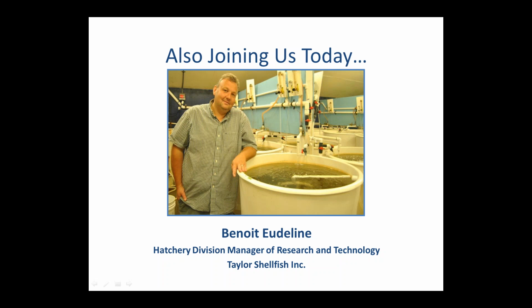I'd like to address another point that Todd mentioned about discrete sampling and co-located sensors. It was a very important point that Todd made about discrete sampling and how close can you be to your probe when you take this discrete sample. And I think that's probably one of the challenges we are having in our location, because the water quality can fluctuate quite fast at times, and again, collecting a discrete sample can be quite challenging, to make sure that you have the same water that the probe is measuring.